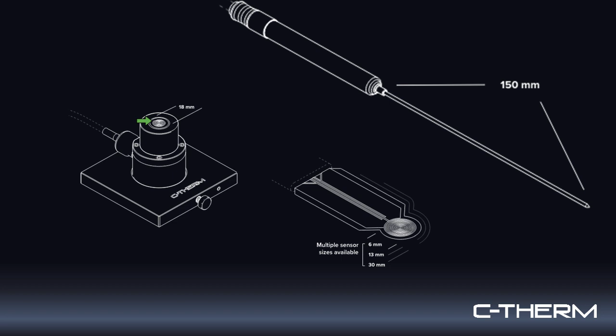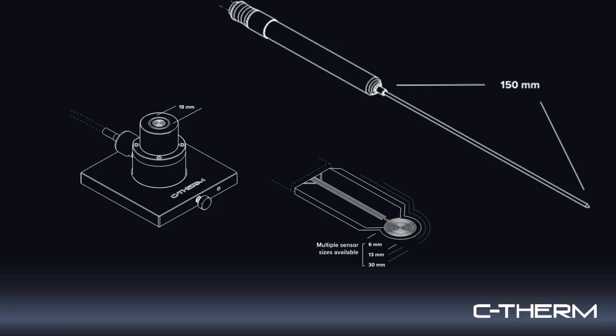So our simplest and easiest, most versatile sensor is the MTPS. It also offers the advantage that it's a single-sided sensor. So in this one, all you do is place the sample on top of the sensor. With the TPS, you'll sandwich the sensor in between two homogeneous samples. So some different sampling requirements as well. The active area for the MTPS sensor is 18 millimeters in diameter, so that's the minimum sample requirement for working with the MTPS method. I'll detail a little bit more the theory of operation of MTPS in the next couple of slides, just where that is going to be specifically referenced in Dr. Landry's work. But this gives you the high-level specifications for these different methods.